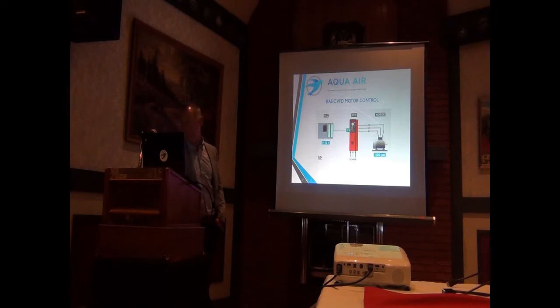The motor's going to run at about half speed. You get half your capacity in the system, so you're adjusting or varying your system to meet the demand, which is more efficient. If you keep tighter control of your system, it tends to be more efficient, and it only meets the demand. It doesn't come full on and full off. It's varying everything, including VFDs, which are often used on other parts of the system, pumps and all that, so everything's slowing down just to meet demand. As you can see in this situation, you have one VFD that's controlling one fan.